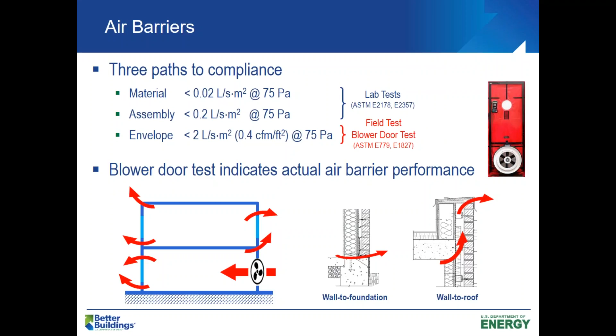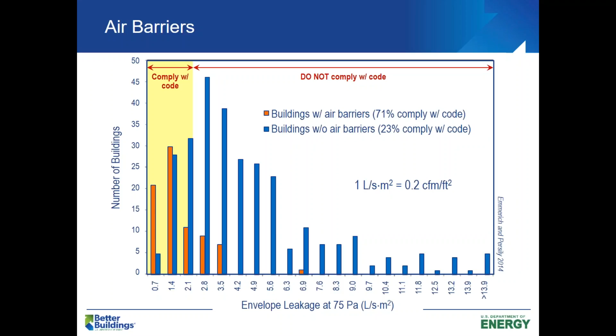This chart here depicts field tests conducted to study how airtight buildings are depending on whether an air barrier was installed or not. According to the results here, for those buildings where an air barrier was installed, about 70% of the buildings were code compliant. While for buildings where no air barrier was installed, only 23% of the buildings were airtight enough to meet code requirements. So this study clearly shows the importance of installing an air barrier to reduce the energy penalties associated with air leakage.